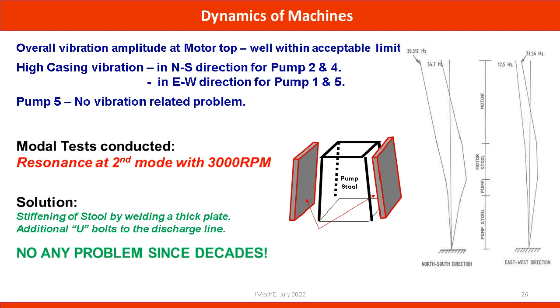So if you see some frequent failure, understanding further becomes important. And when we say modal test, in the industry it is very known as a bump test, which may not be good. Because when you are saying bump test, you may not be using a hammer, you may not be doing the right signal processing, you may not be relating with the theory, you may not be finding the correct natural frequency, you may not be finding the correct mode shape to understand why it is happening. So this is very important to understand, and that's the reason why I'm saying it is good to have a good understanding of the concept and theory.